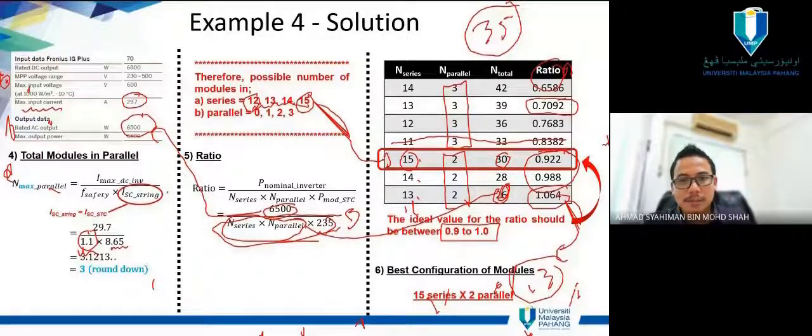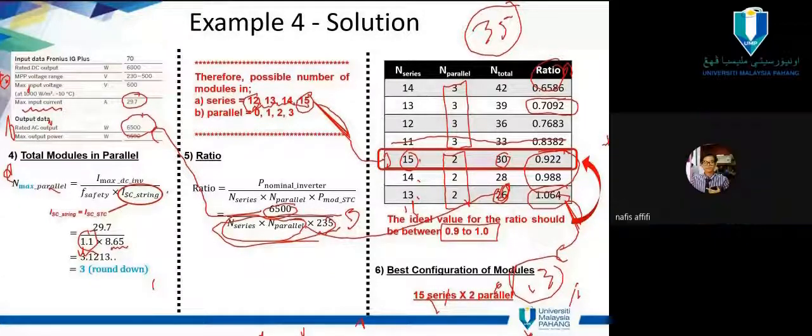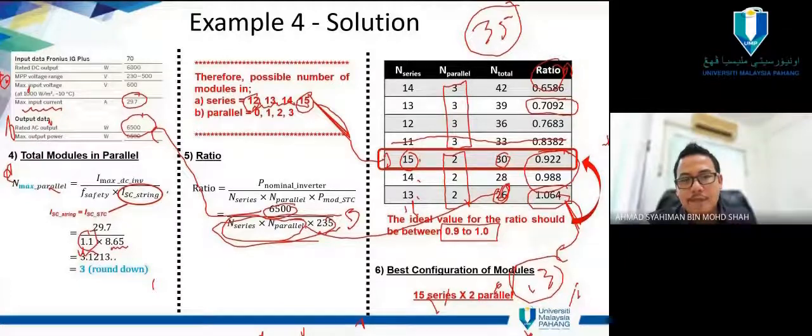Yes, sir. Kalau saya cakap ratio tu 1.3 kan, apa maksud dia? Tadi saya sebut, kalau nilai dia 0.7, itu maksudnya bahagian bawah lebih besar kan? Ya. Bahagian bawah besar maksudnya inverter tu terlalu kecil. So dia rugi lah, satu kerugian, undersizing lah. Sebab kita patutnya dapat supply yang lebih besar, tapi because we are using the small inverter, so we cannot maximize our output to the TNB.